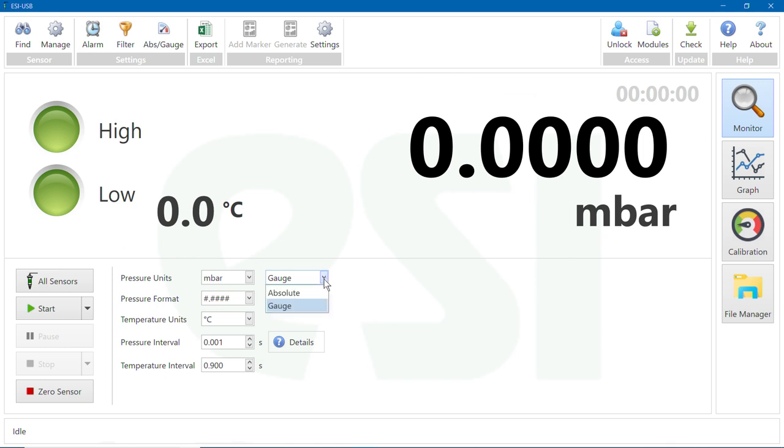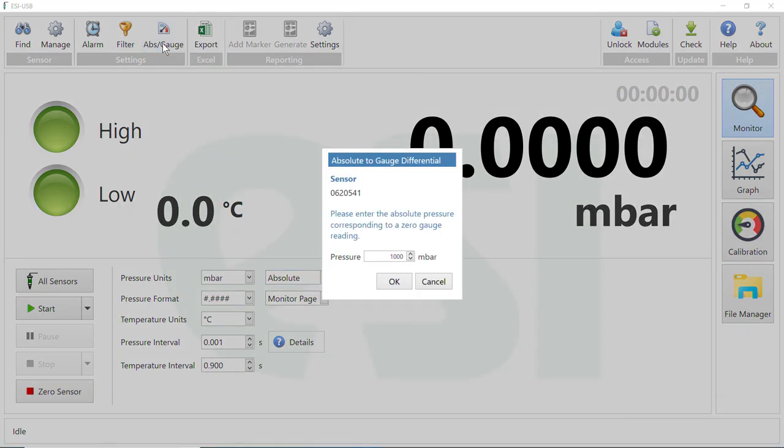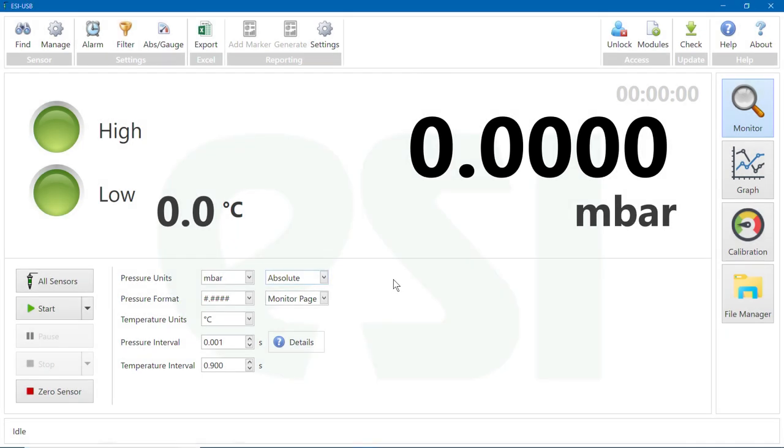A barometric reading will need to be entered before starting a test. To do this, select the ABS gauge icon in the Settings section at the top of the monitor screen. Here the barometric reading can be entered.